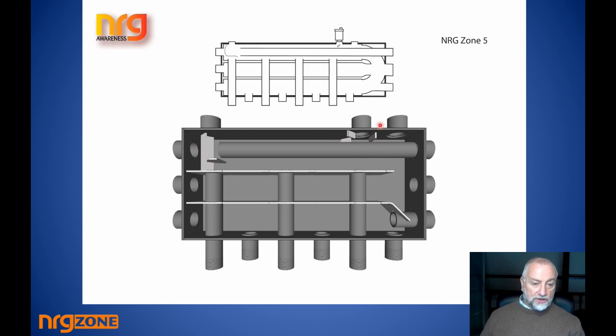I will now draw your attention to the air trap at the top of the unit, because when the water slows down as it passes across the top chamber and the air collects at the top, that's where the air is released.